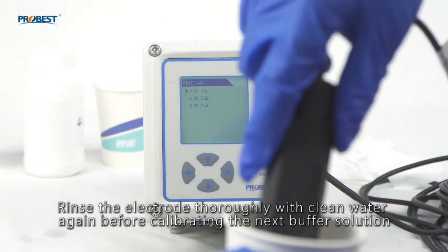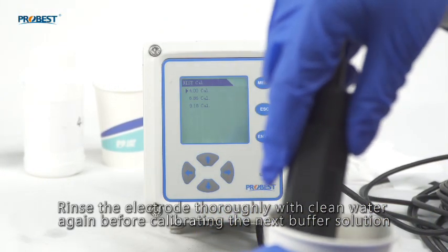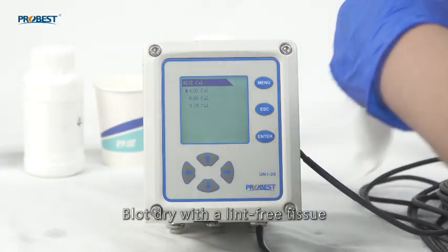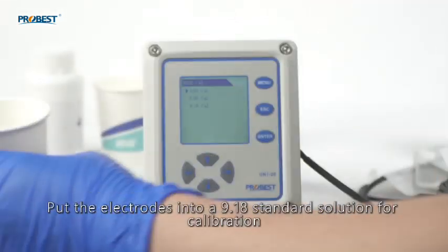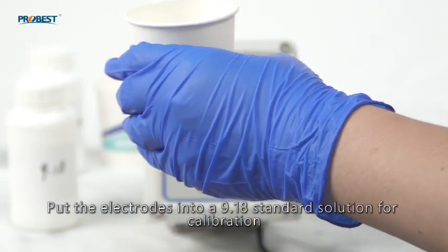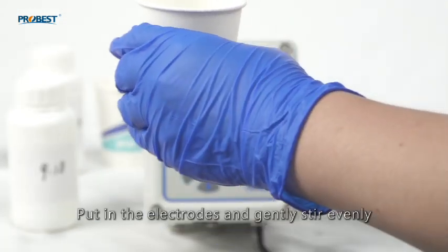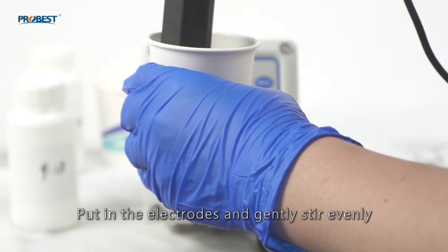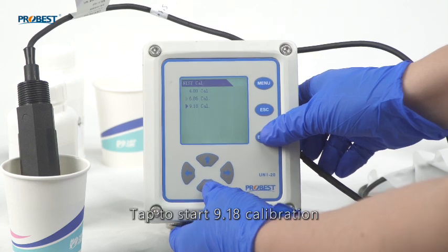Rinse the electrode thoroughly with clean water again before calibrating the next buffer solution. Blot dry with a lint-free tissue. Put the electrodes into a 9.18 standard solution for calibration. Put in the electrodes and gently stir evenly. Tap to start 9.18 calibration.